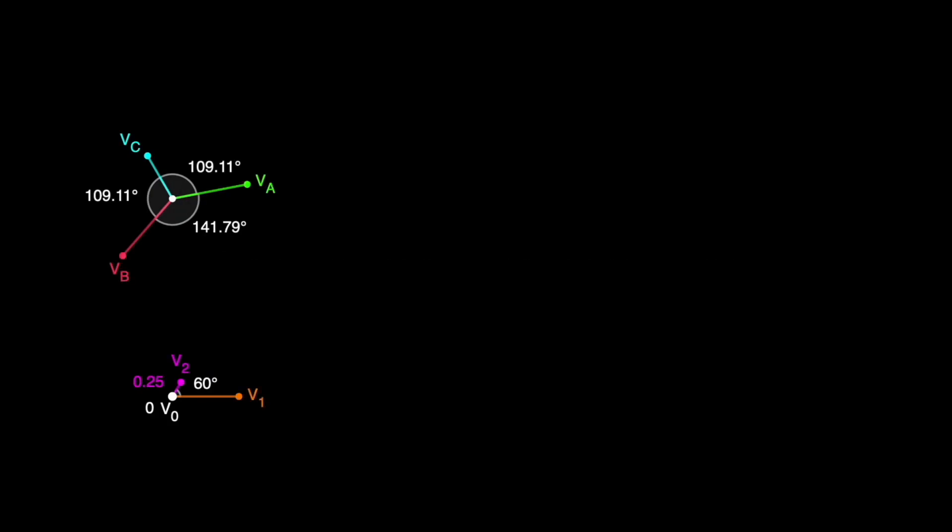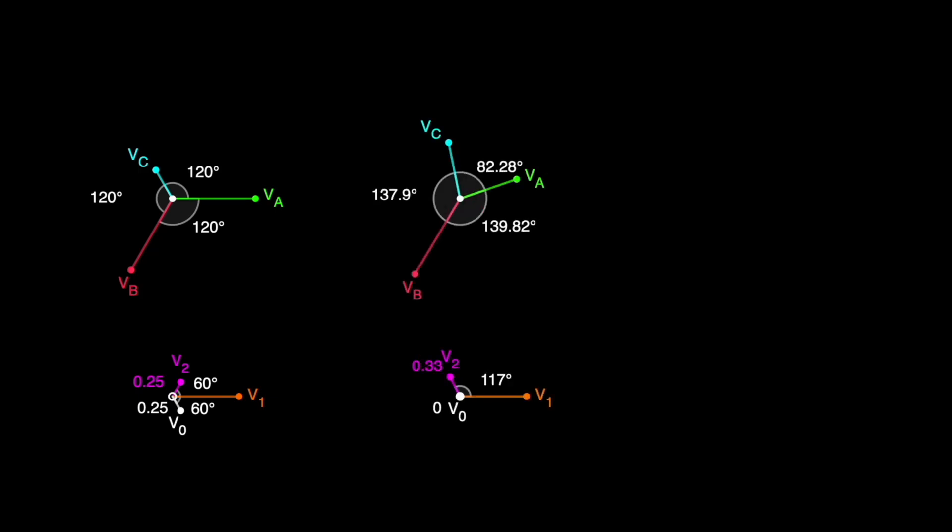In this scene, I'd like you to pay close attention to the angles of the ABC phasors and the angle and magnitudes of the zero and negative sequence components. Note that in the various examples shown here, the ABC phasor angles always have exactly 120 degrees separation when V0 and V2 have the same magnitude and angle with respect to V1.